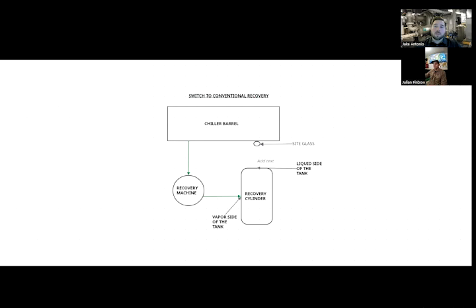I'll close out this one. The other thing to notice here is we're not using any manifolds, right? And your standard gauges, where when you're doing conventional, typically you have a manifold and you're going to be using quarter-inch hoses or 3/8 hoses. So yeah, if you want to start the diagram beside there, that'd be great. Right on. Yeah, and then also note that if you're doing conventional recovery, you don't necessarily have to use manifold gauges. You could go straight with hoses, depending on what other accessories you have for checking out your pressures or accessing your system, right? Yeah, for sure.